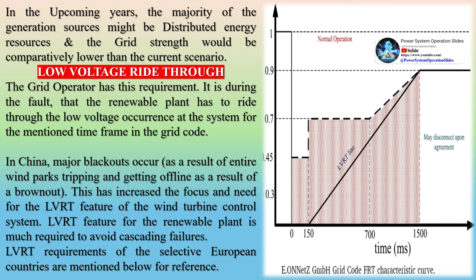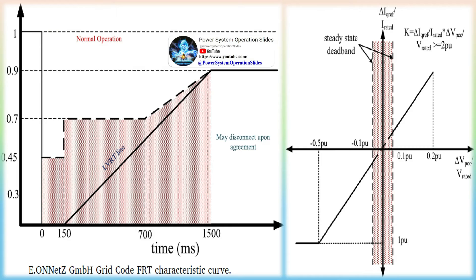Regarding world practice as per grid codes: FRT regulations in Great Britain are specific and pay attention to details such as division of wind turbines into onshore and offshore, different operative fault clearance times, two-ended or three-ended circuits, and different kinds of retained voltage including 30%, 50%, and 85%. FRT regulations in Canada and America have different standards related to their country's classification. The European Grid Code has a harmonized proposal, specific regulation for power park modules, and a wide range of FRT to accommodate the many countries that must follow these rules.